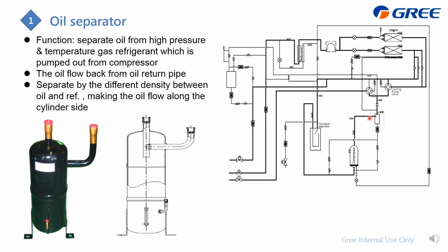Oil separator located here, just between the compressor and the four-way valve. Its function is to separate the mixture of the oil and the high pressure and temperature gas from the compressor. And here is how it works. This is the appearance. There are two pipes, one for in, one for out, and here is for the separated oil coming out. This is the centrifugal type, which works by gravity. The mixture of oil and refrigerant gets in from here, and the heavier oil will touch the cylinder and go down and flow out, as the gas refrigerant will get through this one and here, getting into the system.